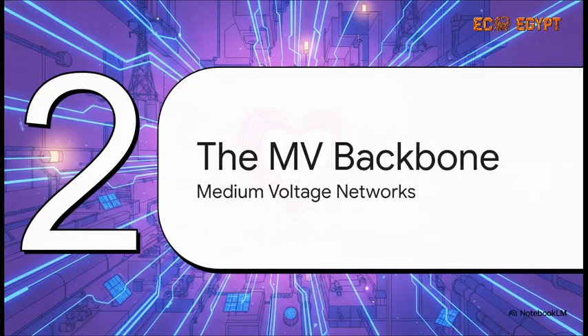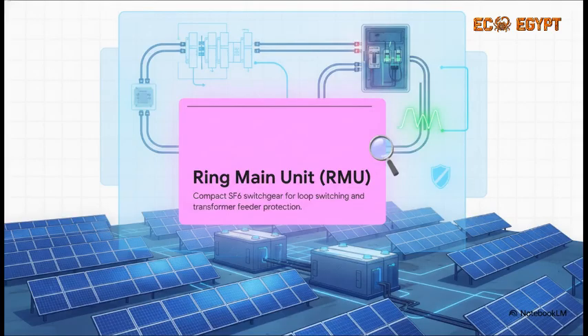Which brings us to Section 2, the medium voltage backbone. In Chapter 4 of our source material, we uncovered this invisible infrastructure that handles all that raw power. And right at the heart of this Level 2 design is the RMU, or Ring Main Unit. If you're not familiar, this is a compact metal-enclosed switchgear that's insulated with SF6 gas. You can think of it as a heavy-duty traffic cop for medium voltage feeders. Its entire job is to connect, protect, and sectionalize. If something goes wrong out there, the RMU is literally your first line of defense. It isolates the fault and maintains loop continuity across these massive PV blocks so the whole plant doesn't go down.